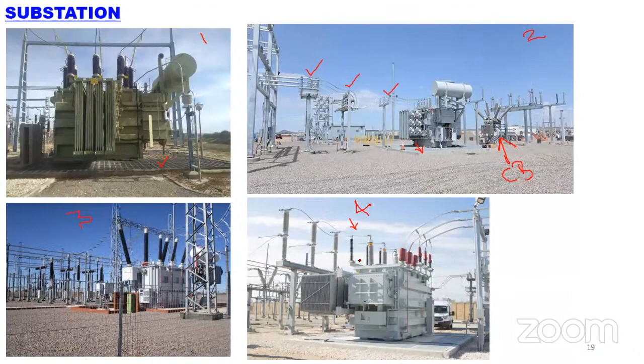Photograph 3 similarly shows a large 220 kV transformer. Photograph 4 is a closer view of the transformer, where you can see a design detail: the surge arrestor is mounted on the transformer itself. Going for a separate structure and foundation would be a costly solution, so some people place the surge arrestor directly on the transformer. This is communicated to the transformer manufacturers, so during construction they provide just a supporting structure to mount the surge arrestor.